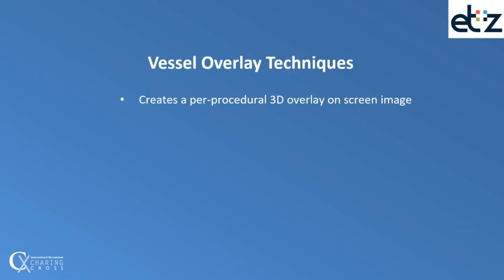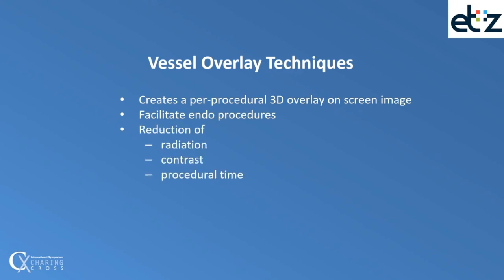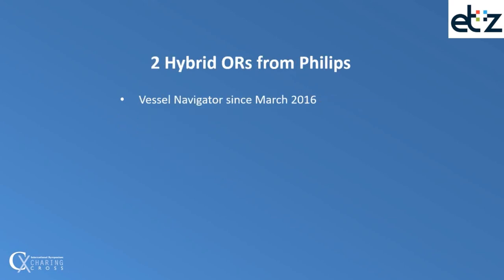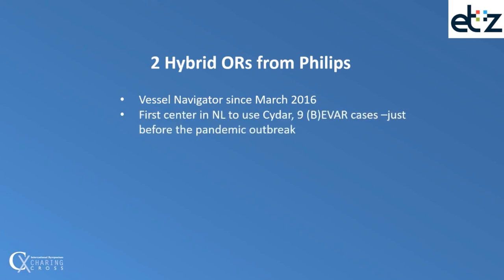Overlay techniques create a per-procedural 3D overlay onscreen, and it facilitates endovascular procedures, leading to a reduction of radiation, contrast, and procedural time. In our hospital we have two Hybrid-ORs from Philips, both equipped with Vessel Navigator, and we are the first center in the Netherlands to use Cydar.